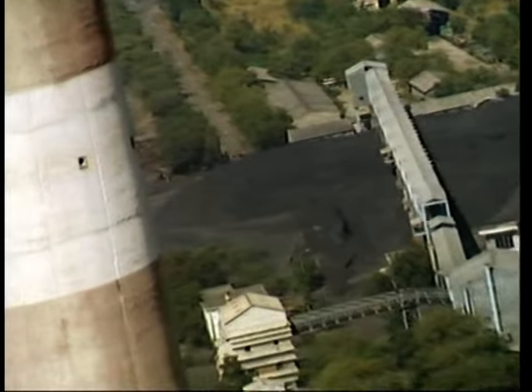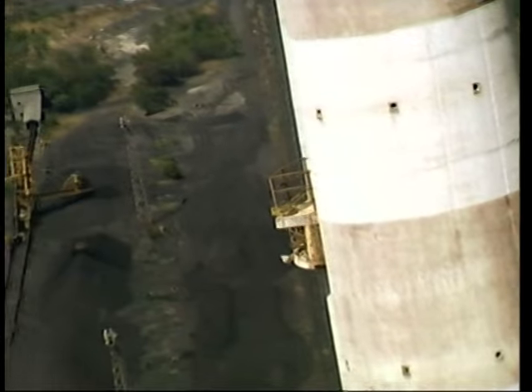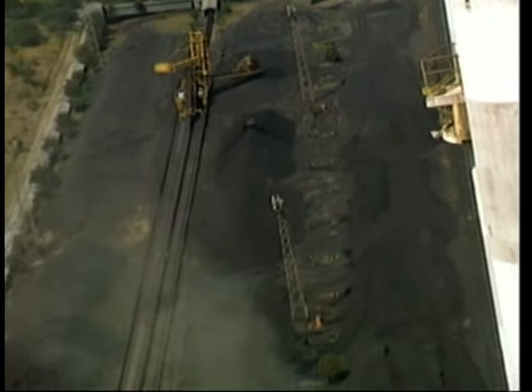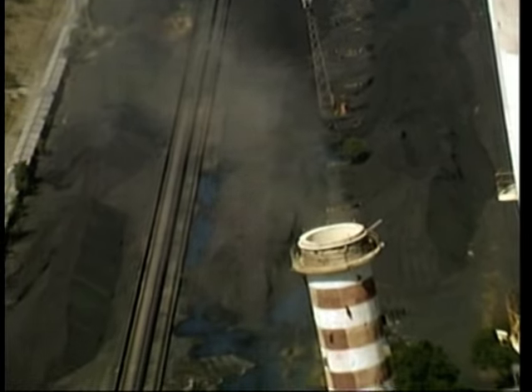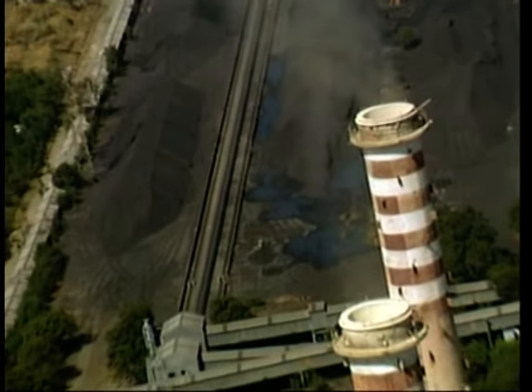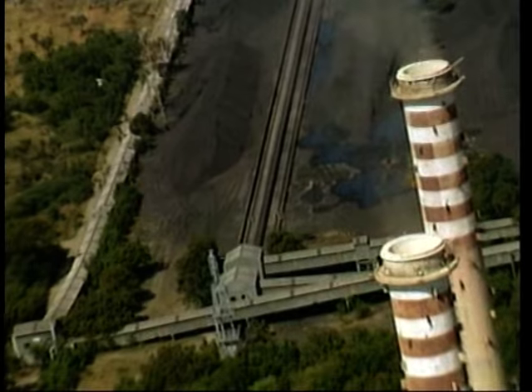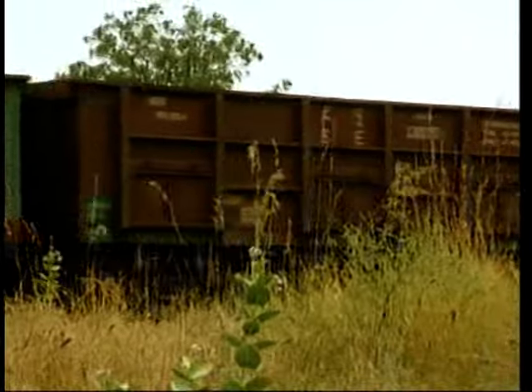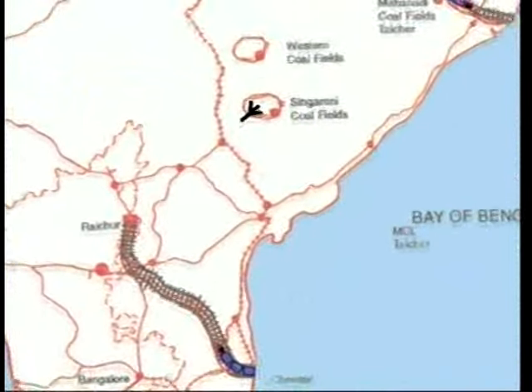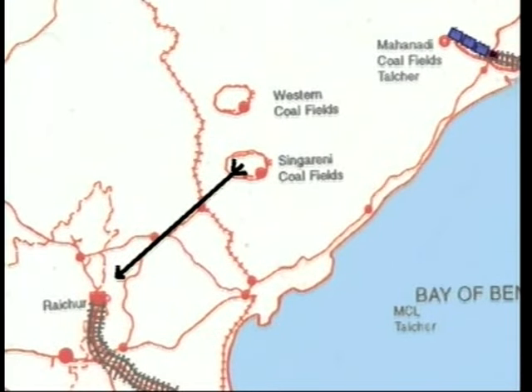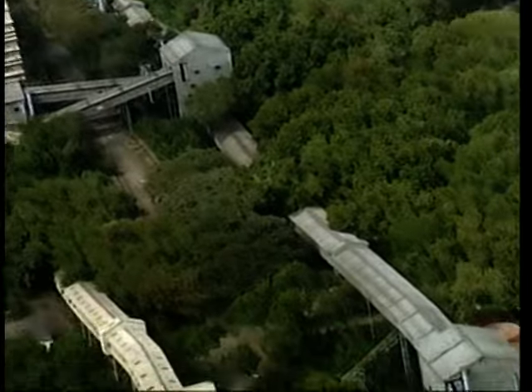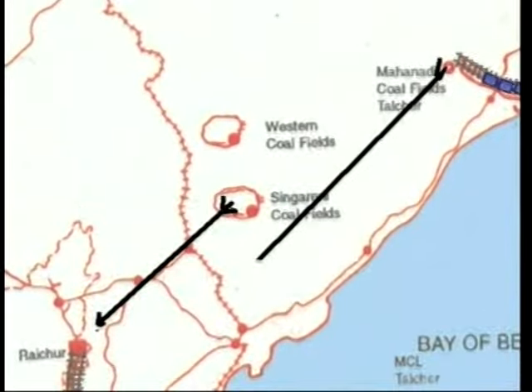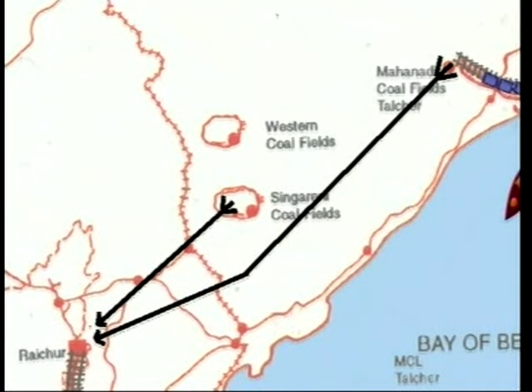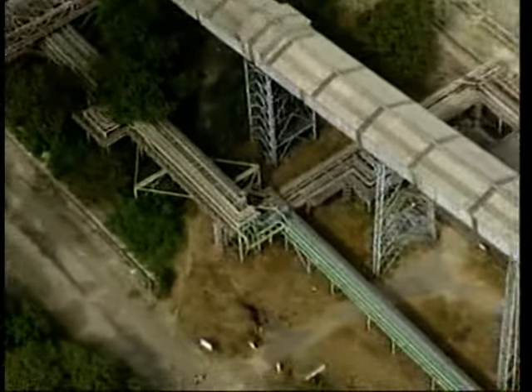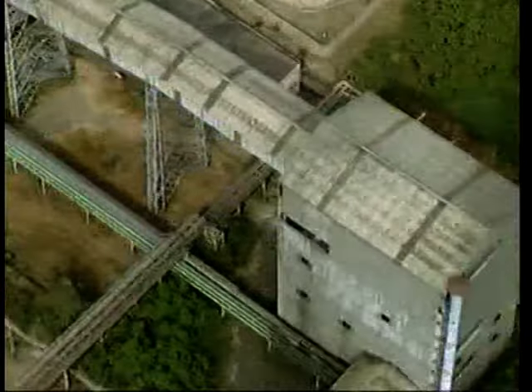The first step in the process is meeting the coal requirements. RTPS's requirement of coal per day is 12,000 to 14,000 tons for the 4 units and 16,000 to 18,000 tons for Unit 6. Coal supply for Units 1 to 4 is procured from Singareni Collieries in Andhra Pradesh and Western Coal Fields in Maharashtra. Coal linkage for the expansion Units 5 and 6 is from Mahanadi Coal Fields in Talcher, Orissa. The coal is made available by the Standing Linkage Committee of the Government of India.